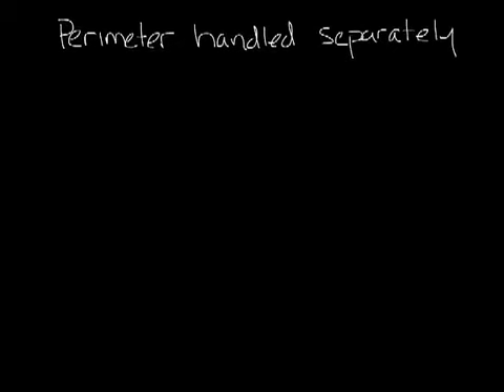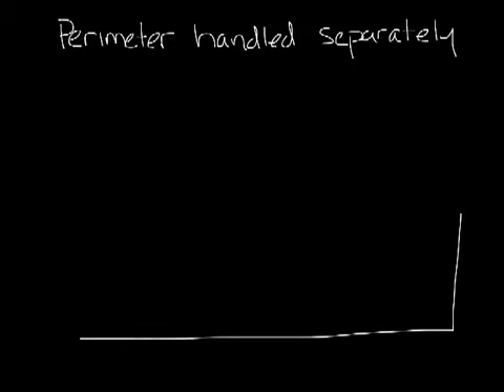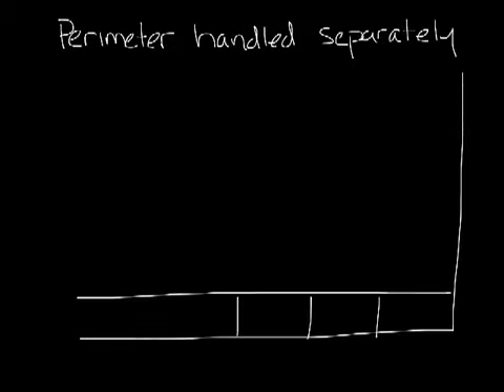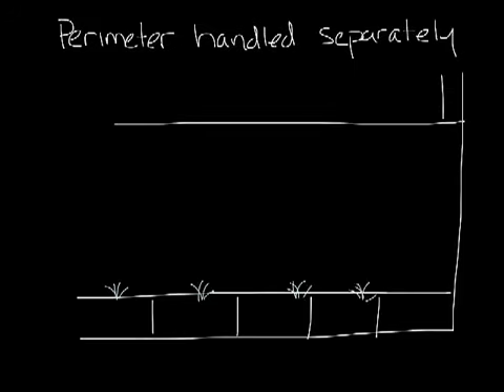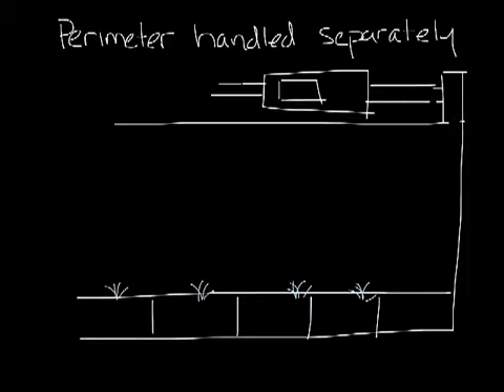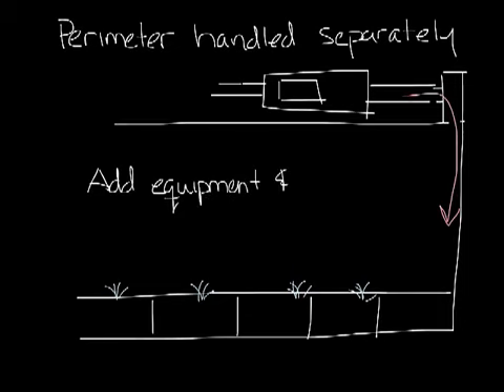As underfloor air distribution gained popularity in the late 90s, the perimeter was usually handled with a fan-powered VAV box, like a standard overhead system. It would look something like this. So let's draw in the raised floor, some swirl diffusers. At the perimeter, you would have a fan box ducted to a slot diffuser, just like you would in an overhead system. This meant that you had to have a ceiling plenum and ductwork in the ceiling, and that could add height and ductwork and VAV boxes to the building, so it wasn't an ideal solution.